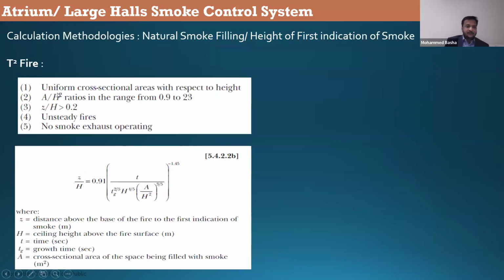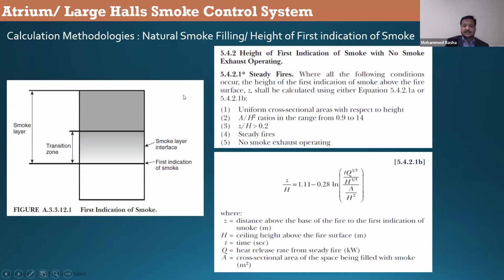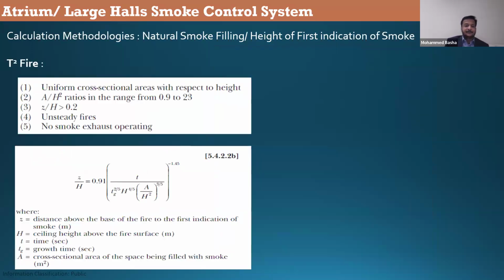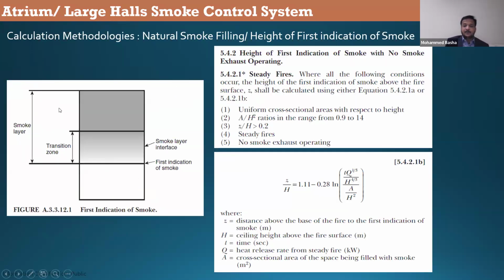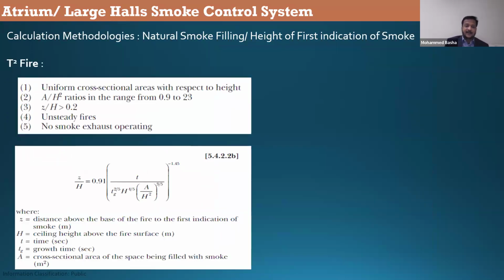This is for T square. Also, there are conditions: uniform cross-sectional area, same. A by H square is up to 23, whereas in the previous slide, it's up to 14. Z by H should be greater than 0.2. Here also greater than 0.2. Unsteady fires, no smoke exhaust operating.